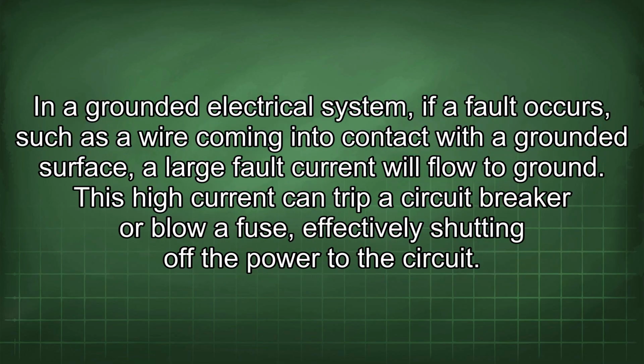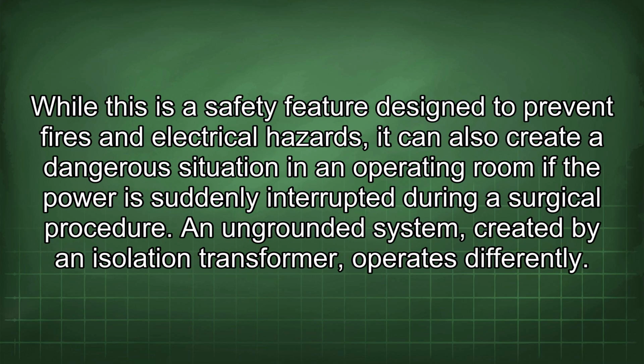In a grounded electrical system, if a fault occurs, such as a wire coming into contact with a grounded surface, a large fault current will flow to ground. This high current can trip a circuit breaker or blow a fuse, effectively shutting off the power to the circuit. While this is a safety feature designed to prevent fires and electrical hazards, it can also create a dangerous situation in an operating room if the power is suddenly interrupted during a surgical procedure.